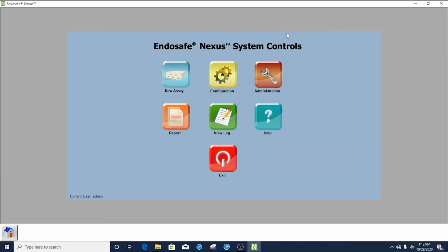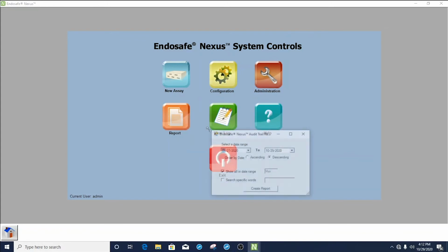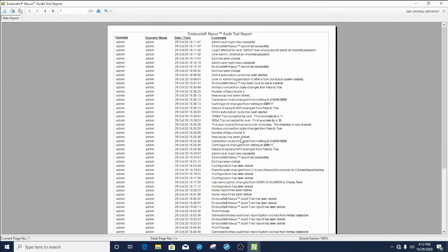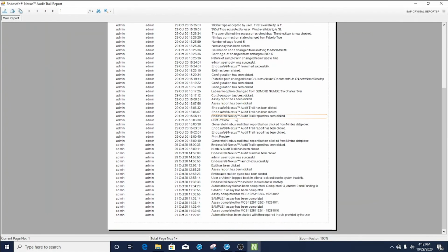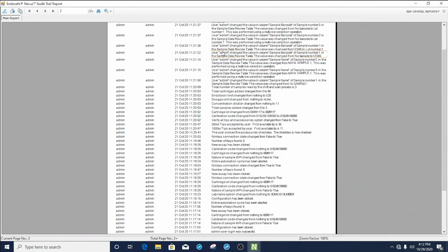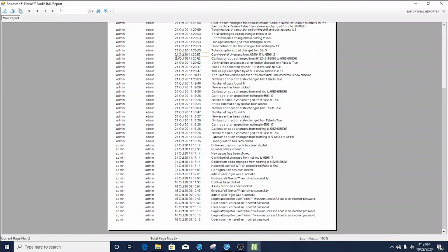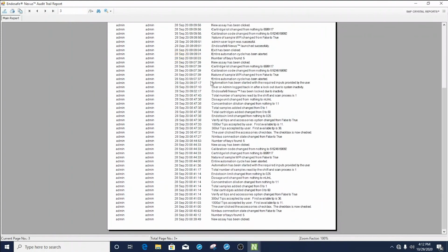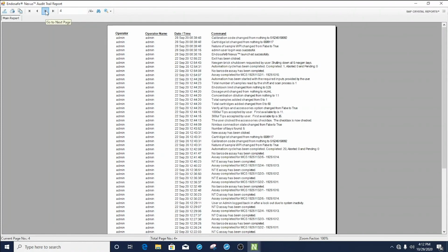The Nexus ensures compliance with data integrity standards, generating 3 separate types of reports to analyze endotoxin results and track the audit trail of both the Nexus software and robotic movements. The audit trail report contains a log of all functions performed by users. It stores all the movements and functions of the Nexus, ensuring the ability to reconstruct critical elements of data generation to give firms more insight into the investigative process during unexpected events.